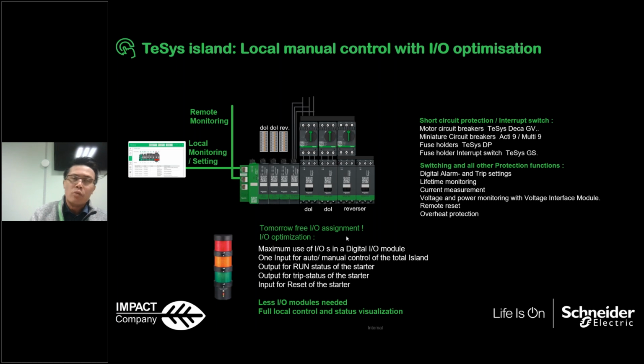And also very important, I don't know whether you know about the I/O card, the I/O distribution card for the PLC, is now in a shortage situation, not only for us, I think for other manufacturers too. So now the lead time is very, very long for the I/O card of the PLC. The TeSys island with the I/O modules, you can take as an alternative for the I/O card to the PLC. Forget about the starters, you don't need starters or other components. With the I/O modules and the bus coupler, you can take this as an I/O card for the PLC because it communicates with the open protocol. The lead time for the TeSys island now is only about 4 to 6 weeks. It's not too long, compared with other I/O cards or I/O distribution modules for PLC, which are counted in months. So basically, this is a possible alternative: using the TeSys island as I/O modules for PLC communications.